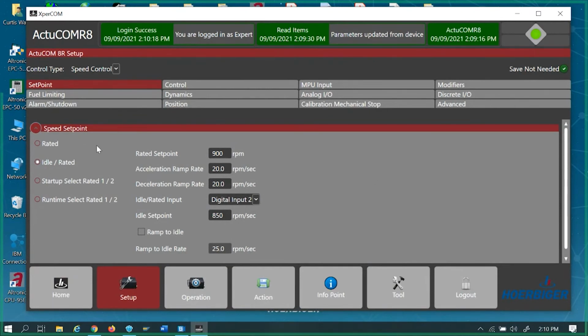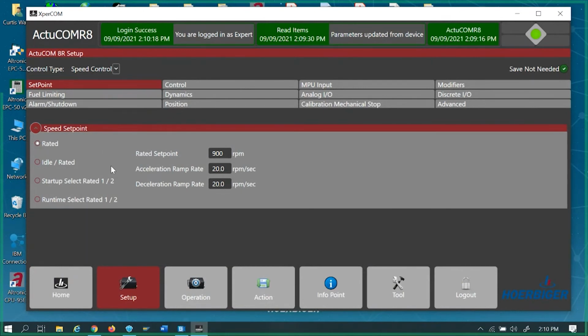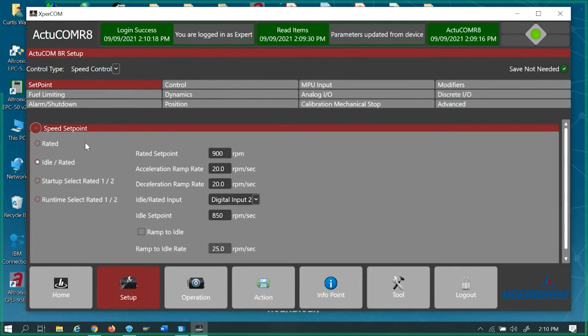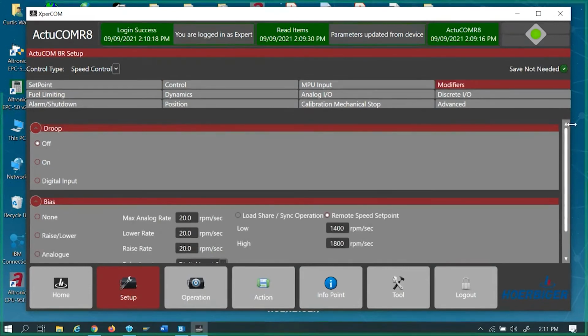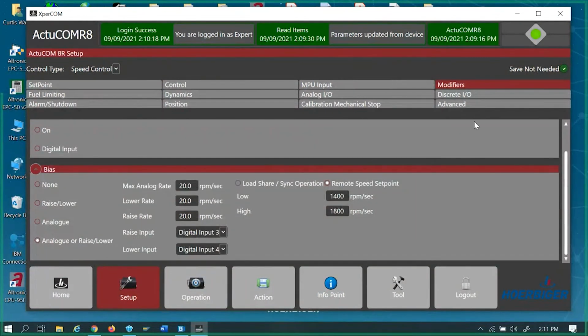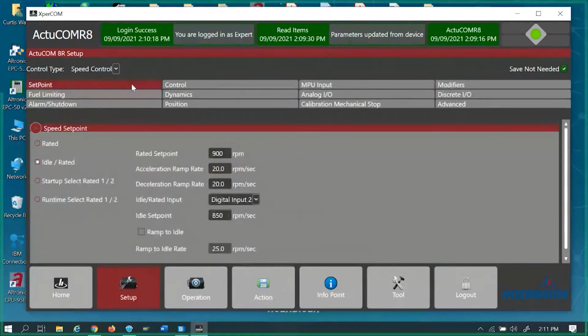Okay, so we have our speed set points. We can have a rated, where you just set a rated number and bring it right up with a toggle switch or something. We have an idle rated, where we can bring it up to an idle RPM and then flip a switch and bring it on up to a load RPM. So like here it says rated 900 and idle 850. Basically we start it, it sits at 850, and when you go to rated it goes to 900. On this application I'm using 900 because you have modifiers here that will override about everything that 900 will do. These things are easy to manipulate, but they'll drive you crazy all at the same time.